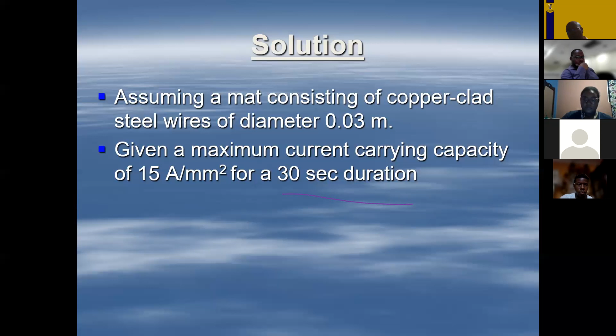For the fault current, we know it was 2,000 MVA on the 132 kilovolt side of the system. Yes. We would have gotten that at the bus bar. Yep. So we know that the fault current would be 8.74 kiloamperes. Yes. And that's a three-phase fault current. Yeah. Giving a corresponding current capacity of 12.36 amperes per square millimeter. So we know the area.